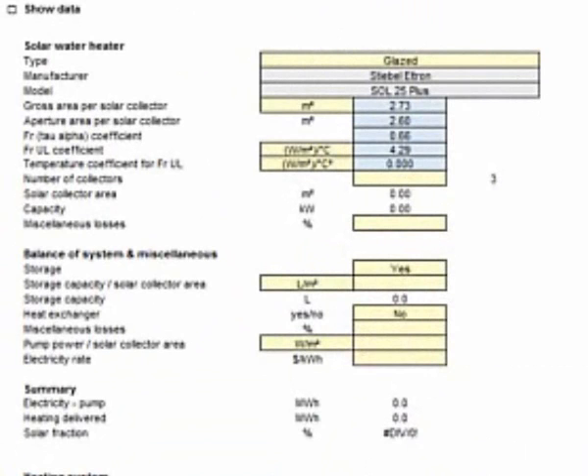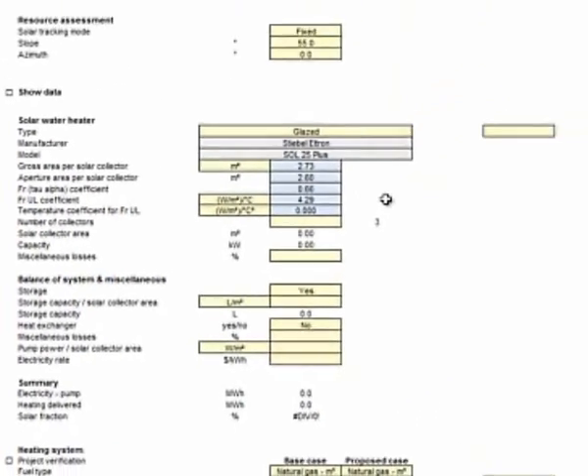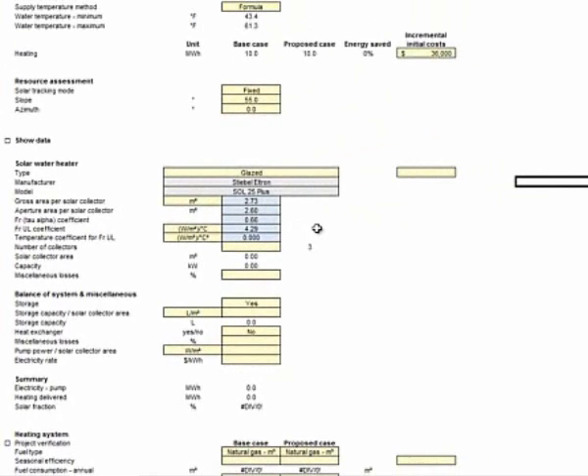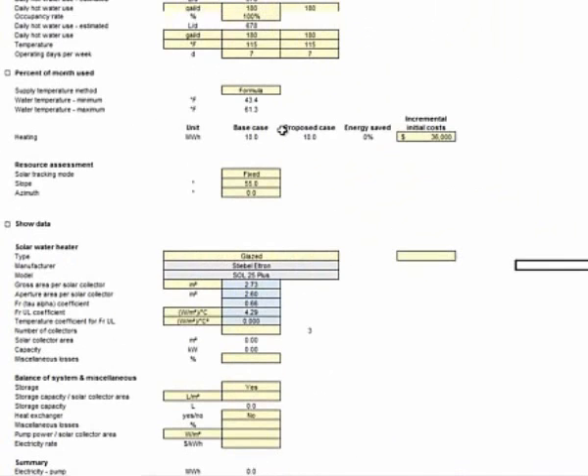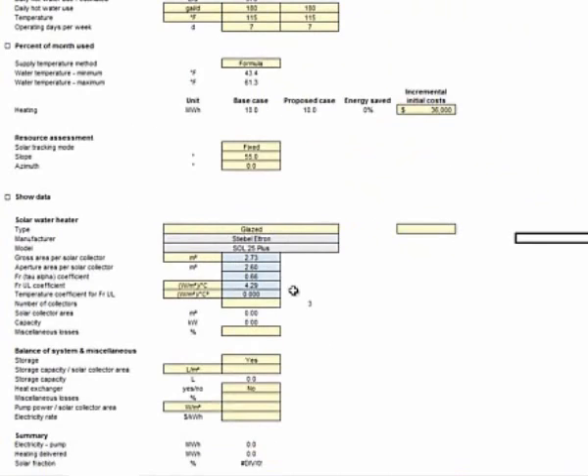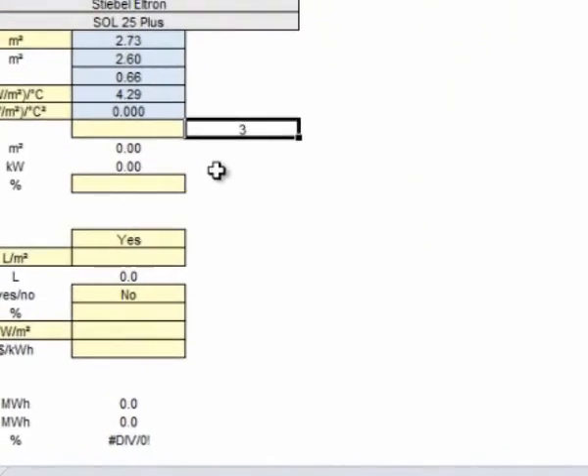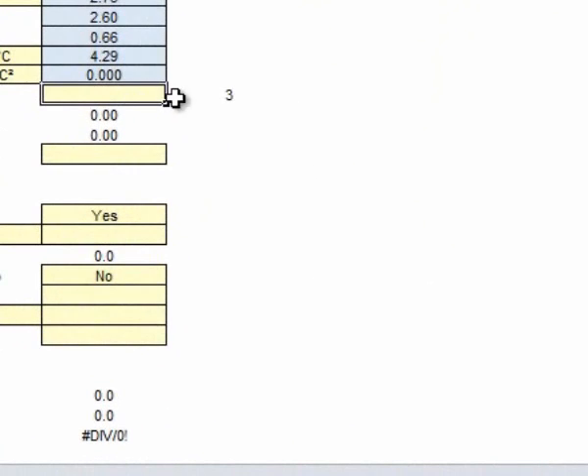That's going to import into here the various parameters of how much energy coefficients and solar collection and all that that we have. If you notice right here, RETScreen is recommending that in order for me to really effectively get this for the 180 gallons of water, it recommends that the number of collectors that I have is 3.